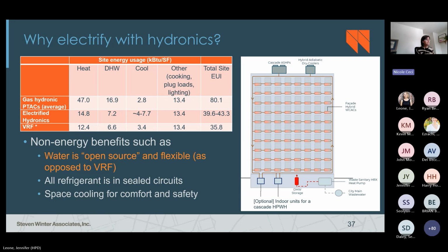Continuing from the previous slide, I want to touch on a few more benefits we see with the electrified hydronic system. Up top I've got some EUI information from energy modeling we did. There's an asterisk next to VRF because I feel VRF systems tend to be modeled with an overly rosy efficiency — some real-world data suggests the COP numbers used in modeling are probably a bit higher than they should be, hence the wiggle room on those EUI numbers. But I want to call out that the electrified hydronics approach in our modeling looks pretty comparable to the energy performance of the VRF system.